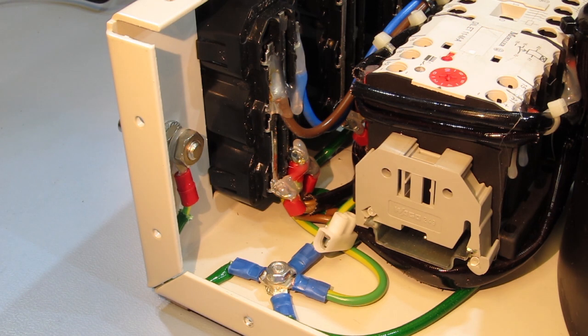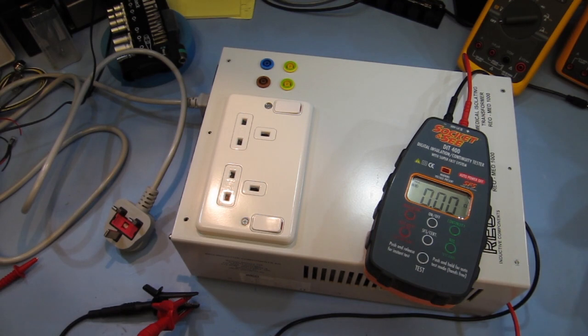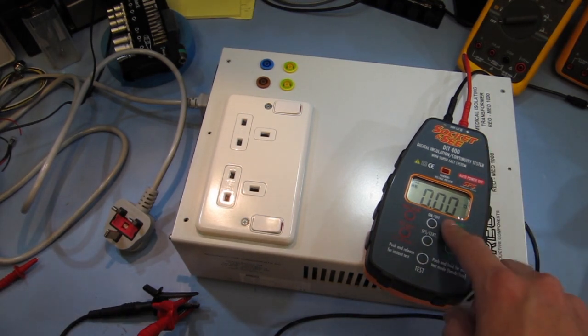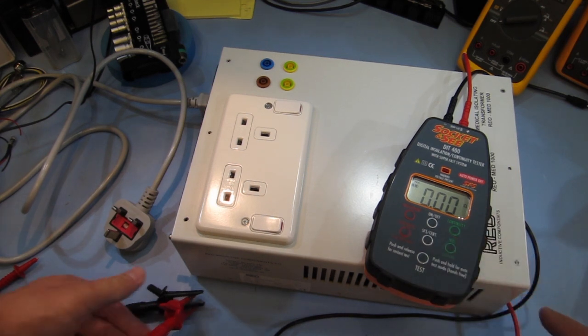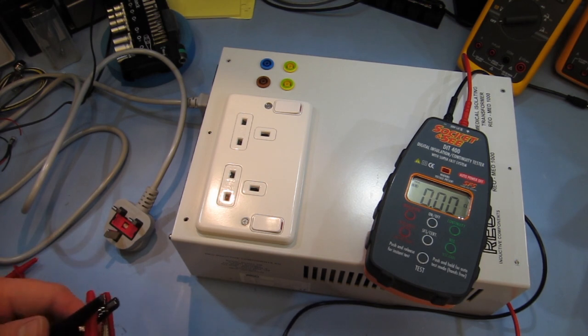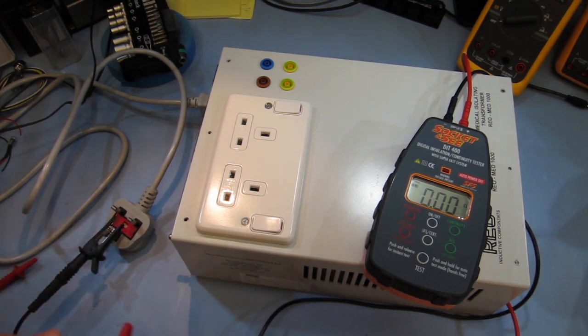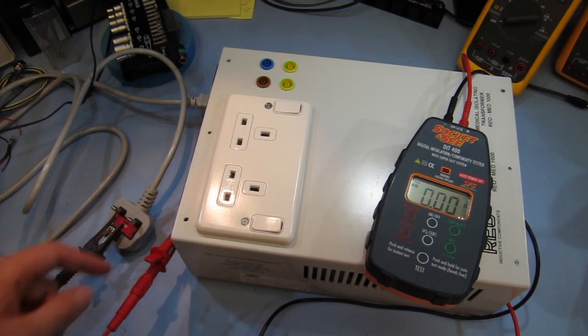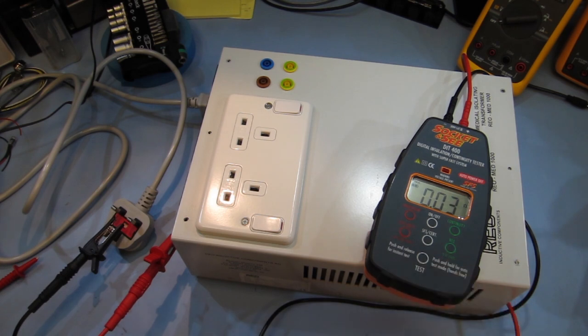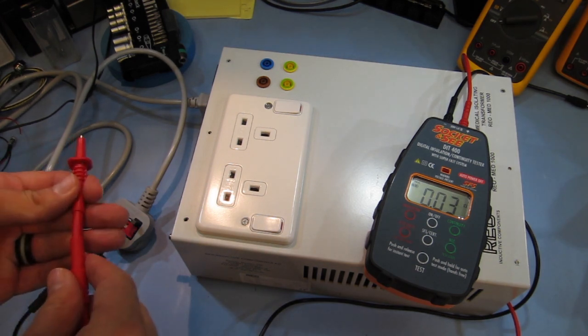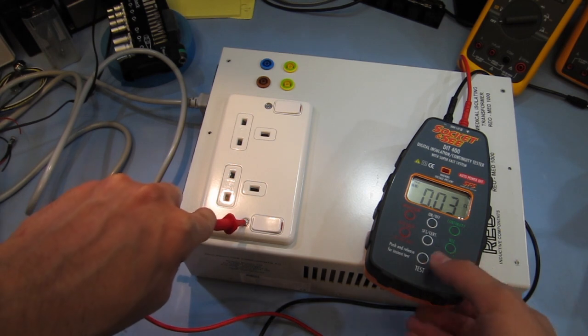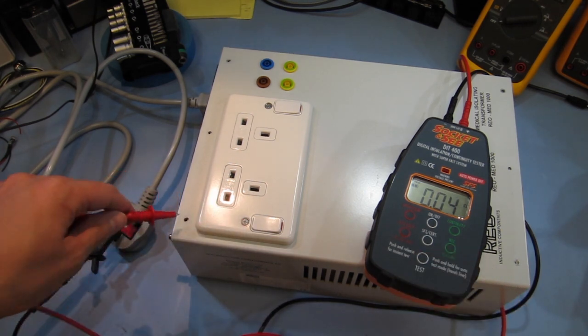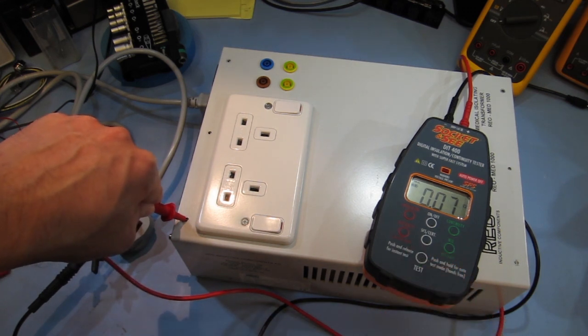So the next thing to do before we power it up is to test it. So I'll just go and get my insulation tester and we can see if it's all connected up correctly. Right, so I've just temporarily put the cover on the transformer, and we've got here a continuity and insulation tester which I've just nulled out the test leads on. So we just want to make sure that our incoming earth connection is connected to the chassis correctly. So I've just put this on the binding post at the front, and if we press test here, we see we've got a nice low reading of 0.03 ohms. We can also check that the top cover also has continuity, and that's also quite good. We'll just test it in here as well, and that's also okay.